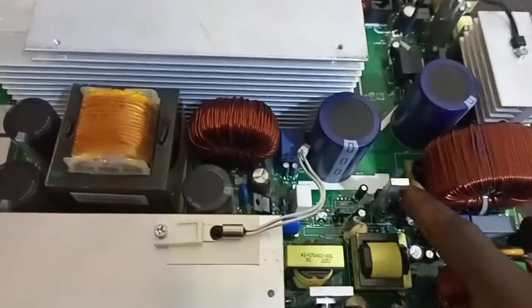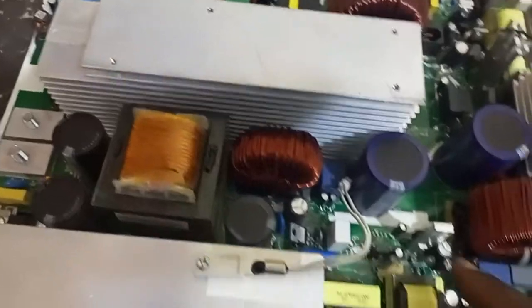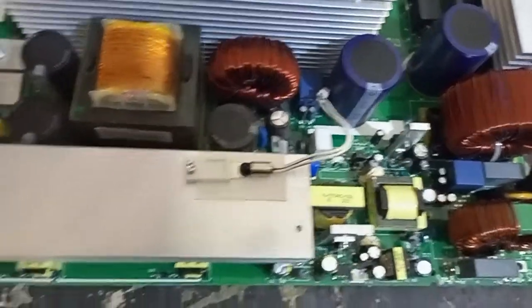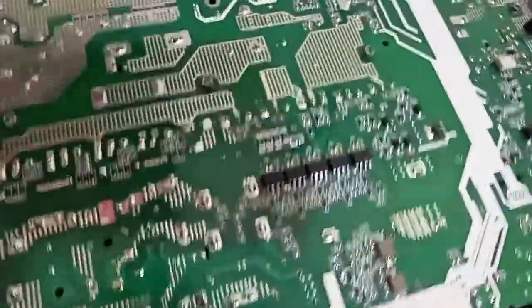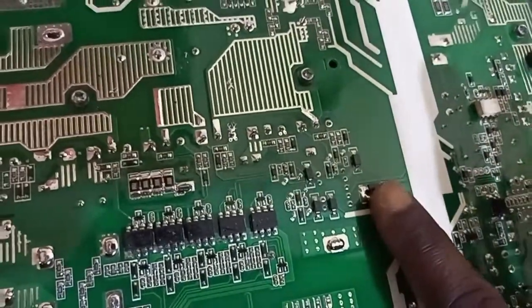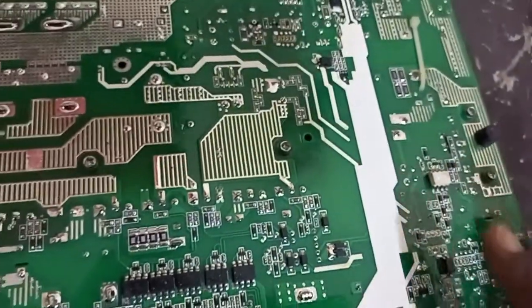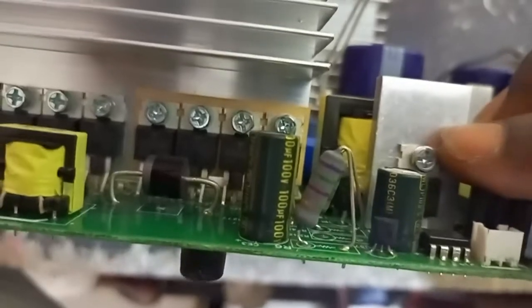Now, if you have a dead set situation in this board, you should look at this circuitry. This circuitry should be the default check. If you have fault F09 or 53, look out for this circuitry. This IGBT may be faulty. You can also check that this component and the circuitry that is connected to this are all okay. If by any chance you have this one blown, if this guy here is blown, please also try to replace this and a whole lot of other things, you get.